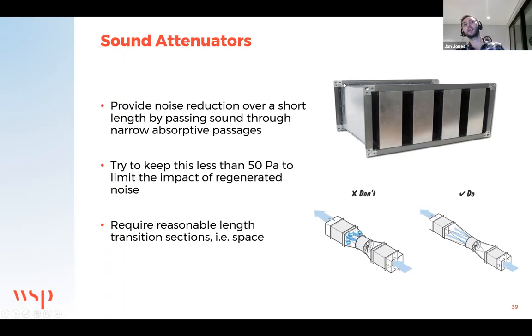The attenuators do add resistance to a ventilation system. That's something that should be considered when selecting fans, to account for the pressure drop that will be added as a result of these attenuators. Typically, a rule of thumb guidance would be to limit the pressure drop on an attenuator to 50 pascals. This limits the impact of regenerated noise. Regenerated noise is basically the whistling sound you get. If you consider an example where you've got perhaps a small grill with a high flow of air coming through it, and maybe something restrictive in the airway, it's the sort of whistling sound you get as air moves at high velocity through a small passageway, essentially. Something to consider in terms of the placing of attenuators in a system, and this ties in with manufacturer literature and data for them as well.